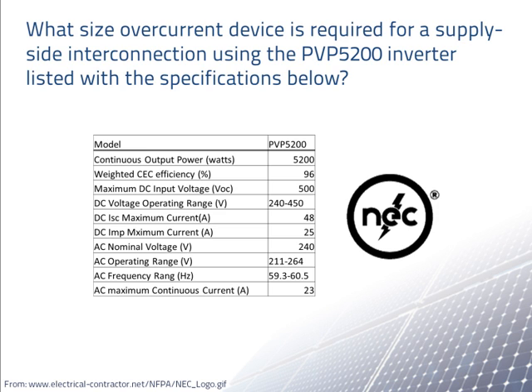NEC 690.8 requires that overcurrent devices must be rated to carry not less than 125% of the maximum current. We usually find the maximum current by multiplying the short circuit current by 125%, but we do not need to in this case because we are already given the maximum rated current.